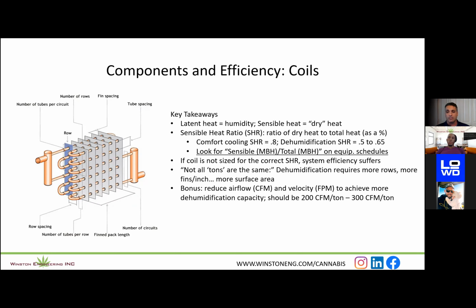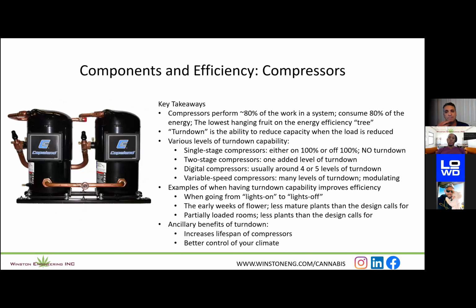So something to look for in your designs is you really want to be in that 200 CFM per ton or 300 CFM per ton range. And just as a side note, generally speaking, for residential or comfort cooling applications, you're really going to be more towards 400 CFM per ton. Again, none of this is meant to be highly technical. It's really just rules of thumb to consider.